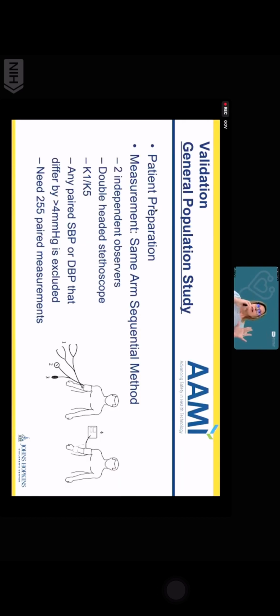So once you've gotten your patient population, your study population, then you're moving on to the actual testing. The testing that occurs, the patient preparation and the actual measurement procedure, is the same as our usual clinical practice guidelines. In our current AAMI protocol, we use what's called the same arm sequential method. And what that means is that the reference cuff is put on one of the arms. You have 2 independent observers. They use a double-headed stethoscope.